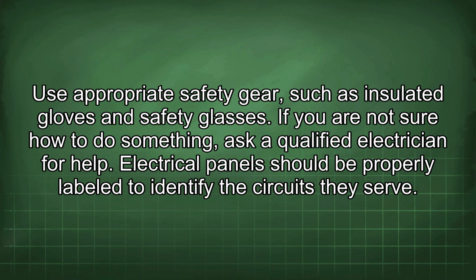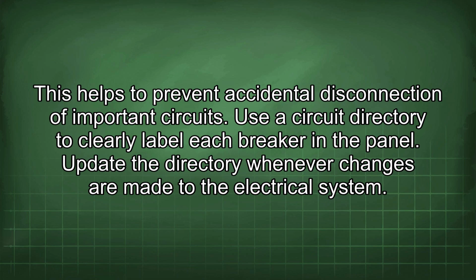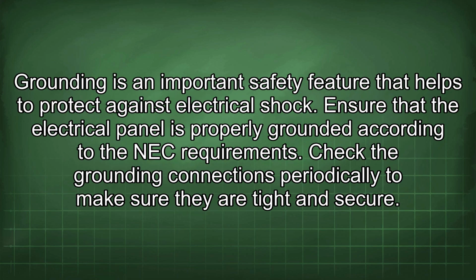Electrical panels should be properly labeled to identify the circuits they serve. This helps to prevent accidental disconnection of important circuits. Use a circuit directory to clearly label each breaker in the panel. Update the directory whenever changes are made to the electrical system. Grounding is an important safety feature that helps to protect against electrical shock. Ensure that the electrical panel is properly grounded according to the NEC requirements. Check the grounding connections periodically to make sure they are tight and secure.